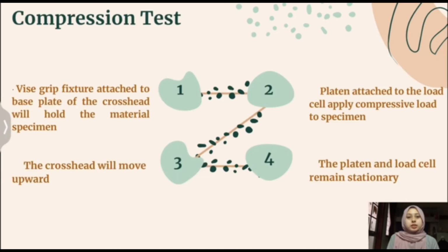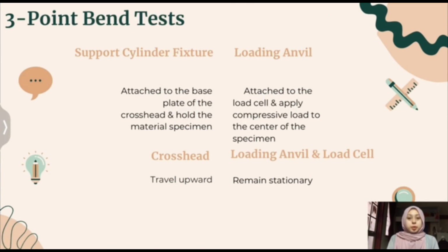Compression test. A vise grip fixture attached to the base plate of the crosshead will hold the material specimen. The platen that is attached to the load cell applies compressive load to the specimen. The crosshead will move upward while the platen and load cell remain stationary. 3-point bend test. The support cylinder fixture is attached to the base plate of the crosshead and holds the material specimen. The loading nose that is attached to the load cell applies compressive load to the center of the specimen. The crosshead will travel upward, while the loading nose and the load cell remain stationary.